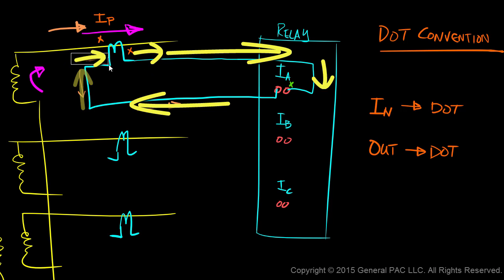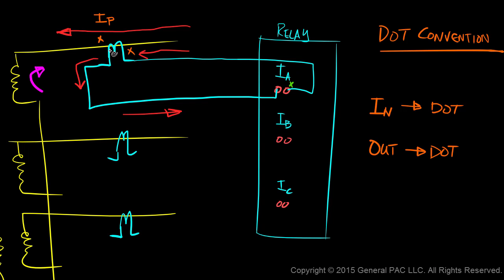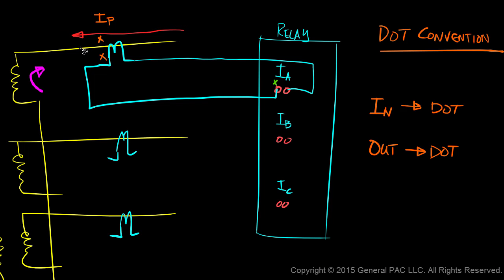What if we had current flowing in a different direction on our primary side? When current is flowing in this direction, we know the CT comes first and then we have the dot. So in this configuration, the current is flowing out of the dot. Current flows out of the dot on the primary side, which means current must flow into the dot on the secondary side, and it'll make a circulating path like this. Now, if our dot on the secondary side was over here, the same rule applies — current flows out of the dot on the primary side means current must flow into the dot on the secondary side.